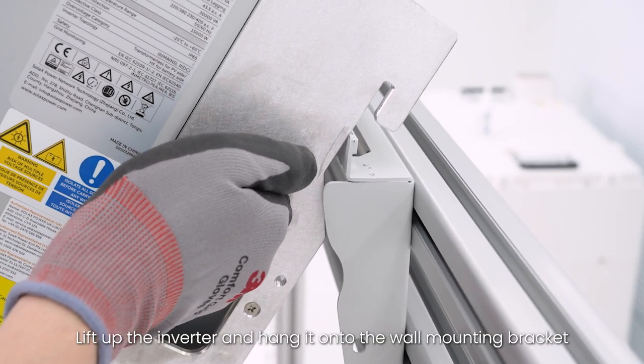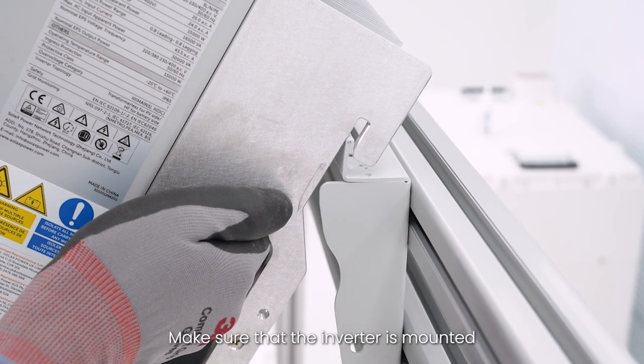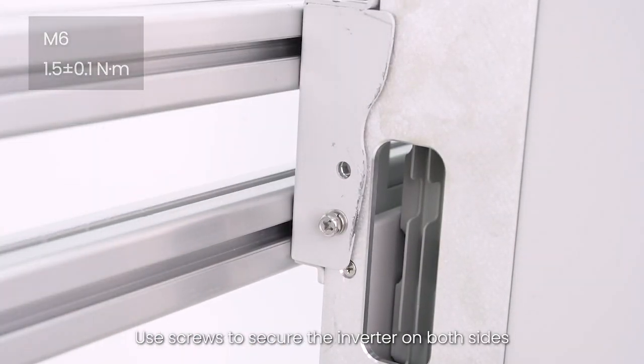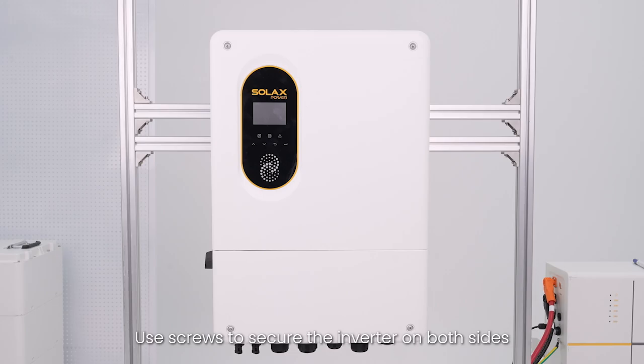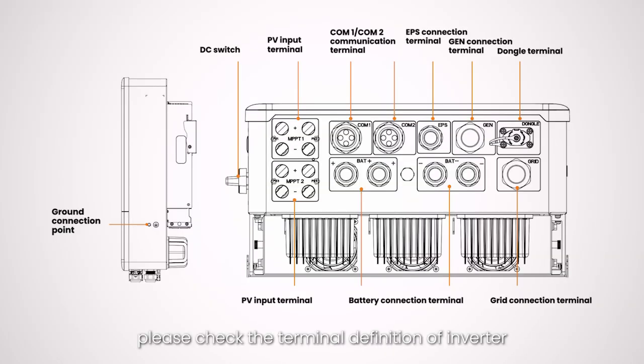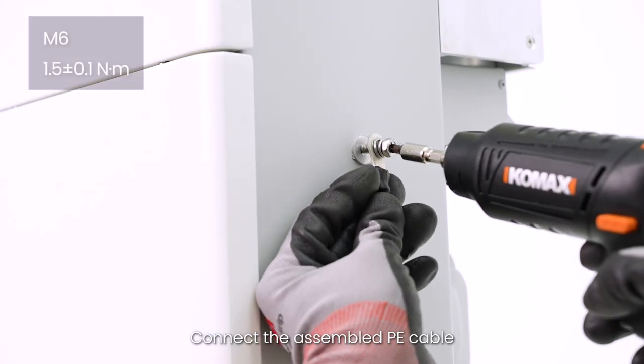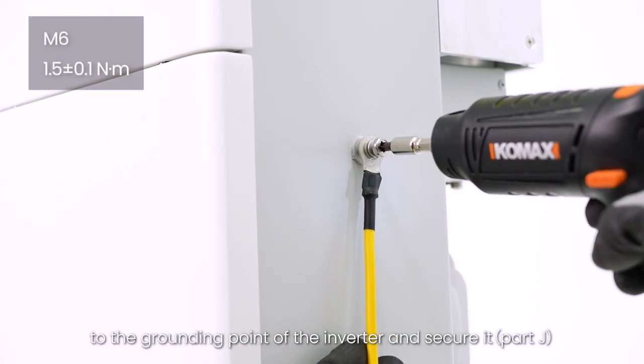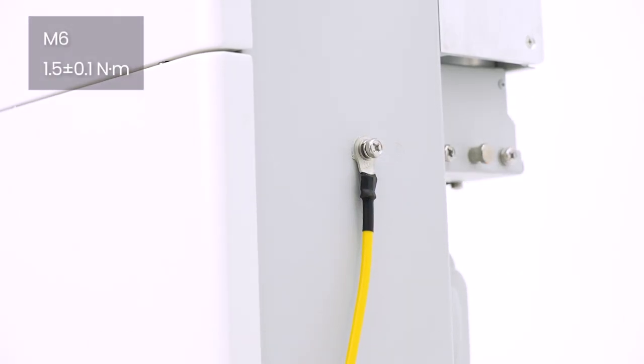Lift up the inverter and hang it onto the wall mounting bracket. Make sure that the inverter is mounted on the bracket as shown in the video. Use screws to secure the inverter on both sides. Before the wiring, please check the terminal definition of inverter. Connect the assembled PE cable to the grounding point of the inverter and secure it.